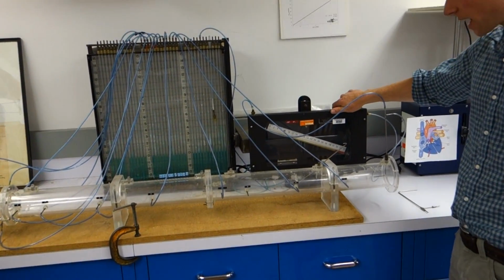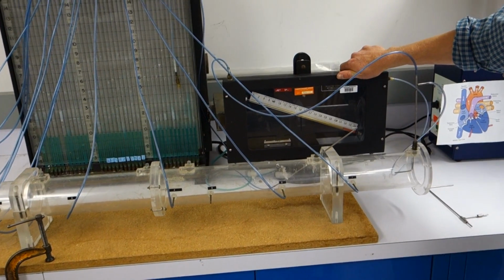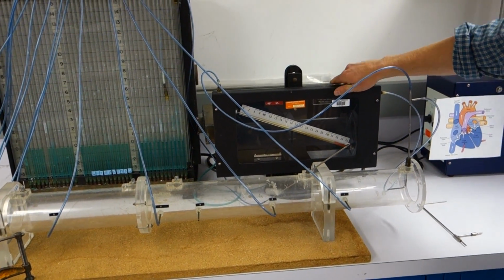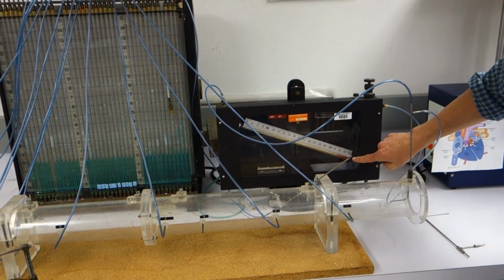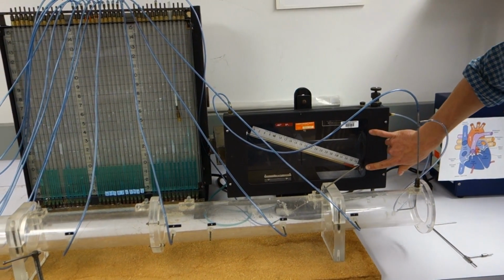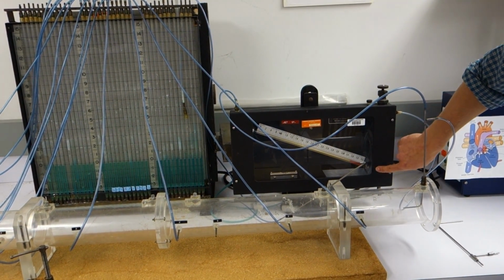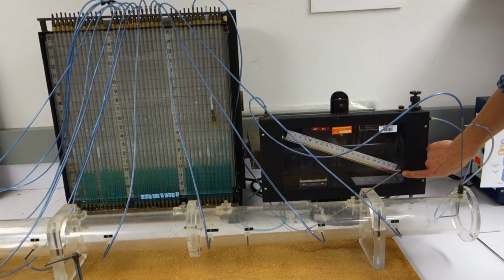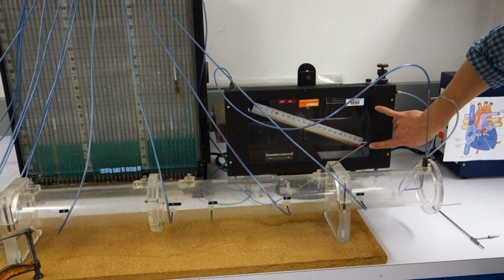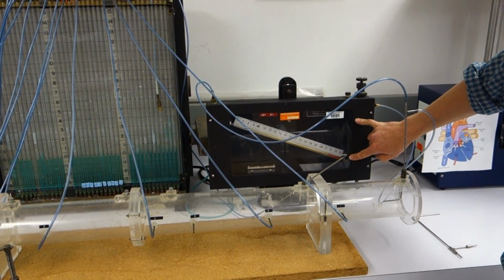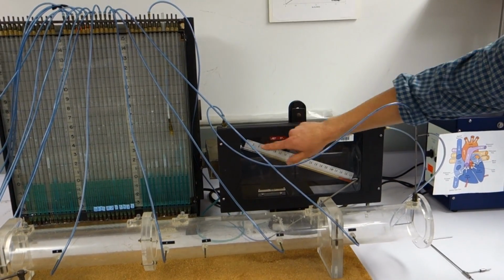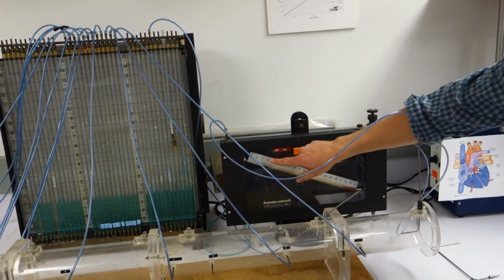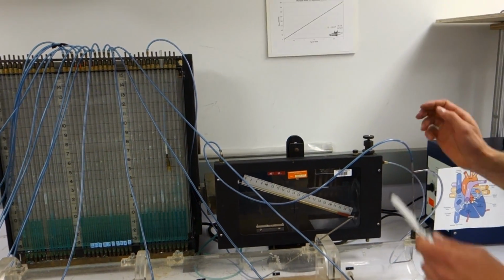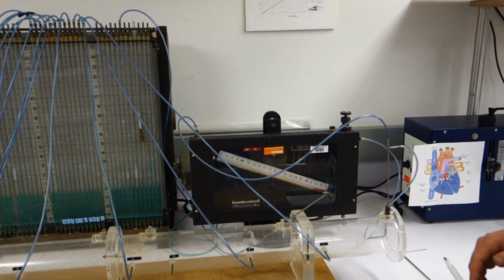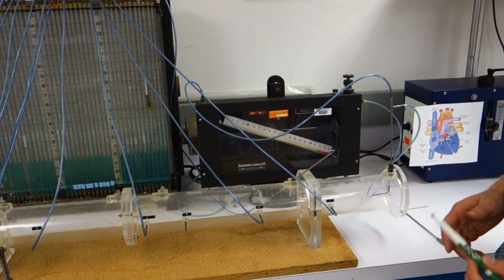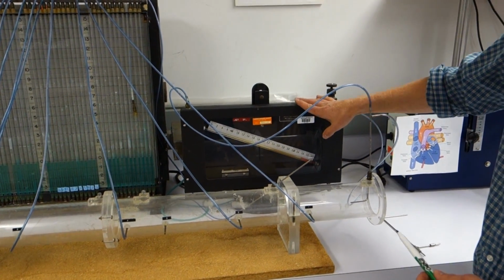The slant manometer uses the same principle as the floor manometer we just talked about. You'll see that the numbers read from 0 to 4, and there's a 4-inch height difference between the bottom of the fluid and the top of the ruler. So that means there's a factor of 3 increase in resolution. This is 4 inches spread across 12 inches, which means we have 3 times the increase in resolution using the slant manometer.